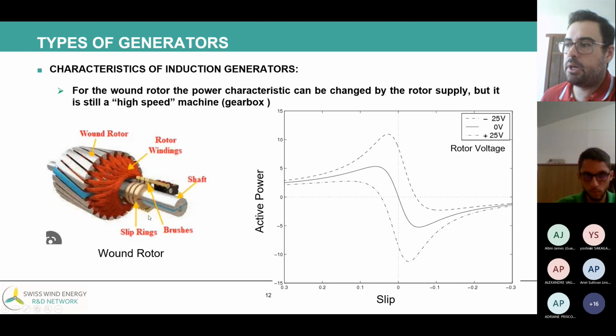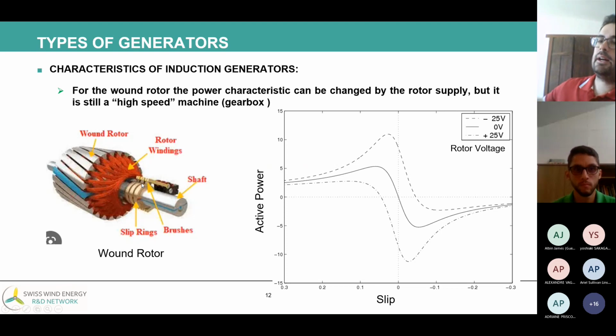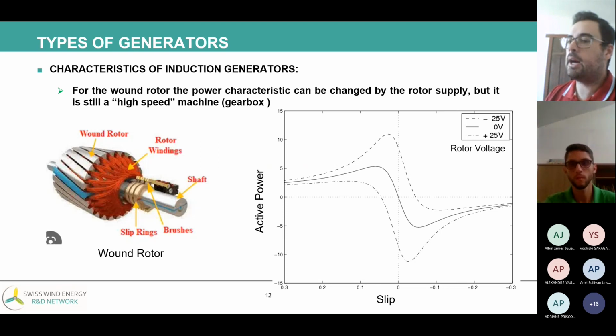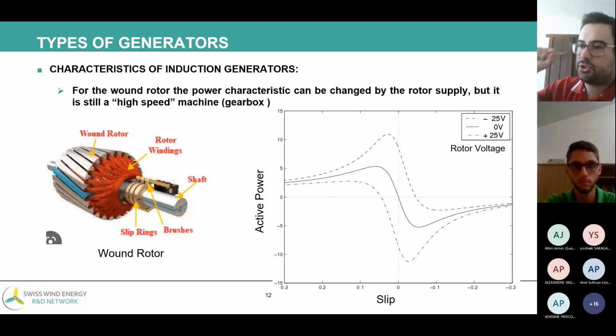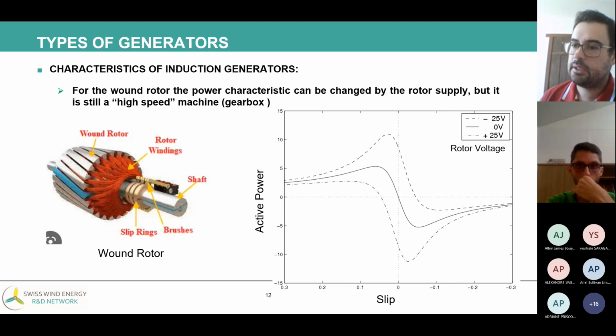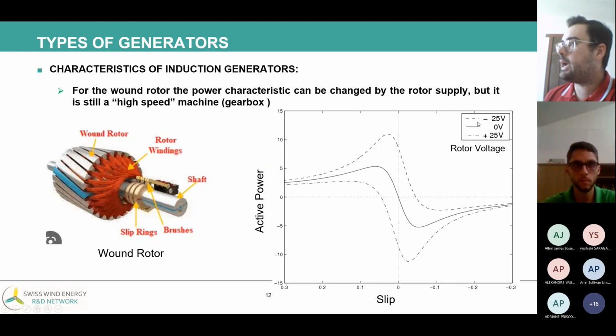And the slip rings and the brushes are a problem because they are very prone to maintenance. At least once a year, it's necessary to change the brushes. And imagine going up a tower of 100 meters to change the brushes, having to stop the machine, and imagine offshore applications. This is a bit complicated. The maintenance of this kind of machine is a concern. The difference between the wound rotor and the squirrel cage is applying voltage to the rotor. It's possible to change the power characteristics of the generator.